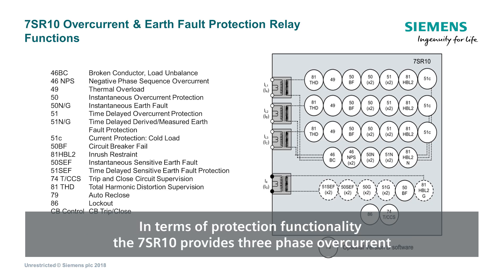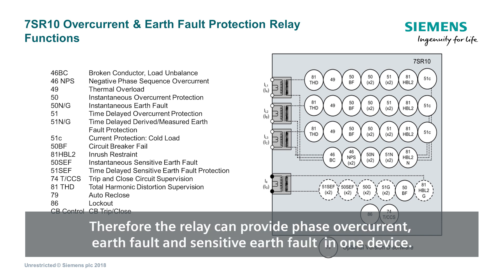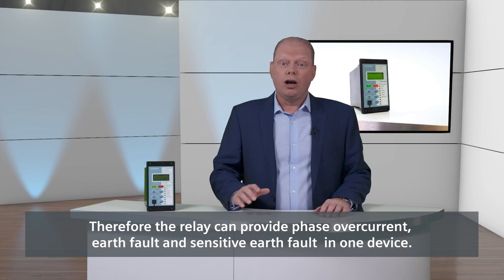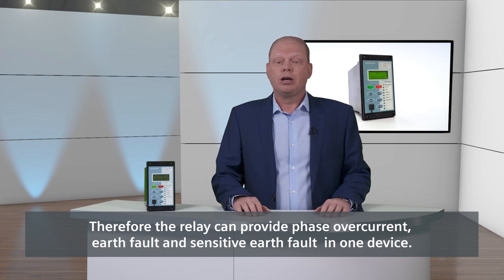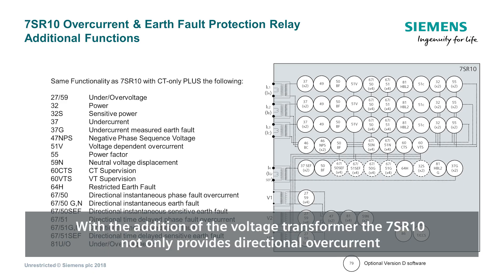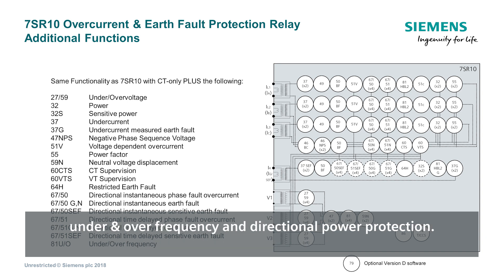In terms of protection functionality, the 7SR10 provides three phase overcurrent and both measured and calculated earth fault. Therefore the relay can provide phase overcurrent, earth fault, and sensitive earth fault in one device. With the addition of voltage transformers, the 7SR10 not only provides directional overcurrent and earth fault but a number of additional functions, including under and over voltage, under and over frequency, and directional power protection.